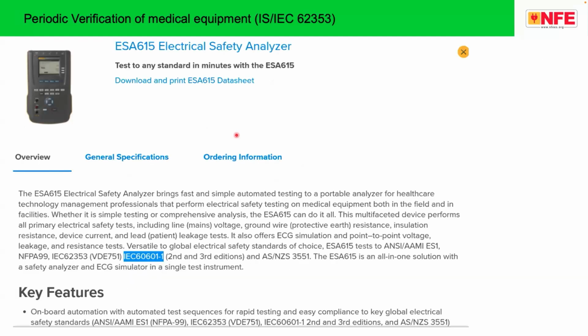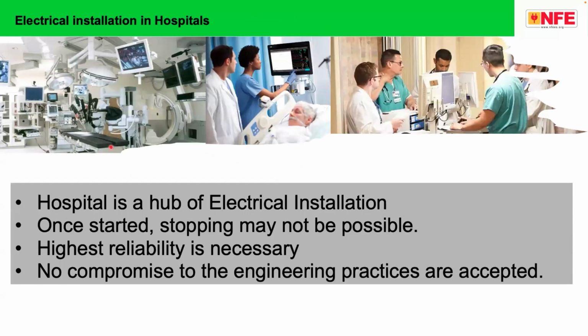The biomedical equipment which you are using is also to be tested as per the standard 62353. This instrument which I am showing on the left is an instrument which can be used for testing the biomedical equipment. Ideally, in every hospital, the biomedical engineer should have this kind of test instrument, and he has to test and ensure that the biomedical equipment is in good condition.